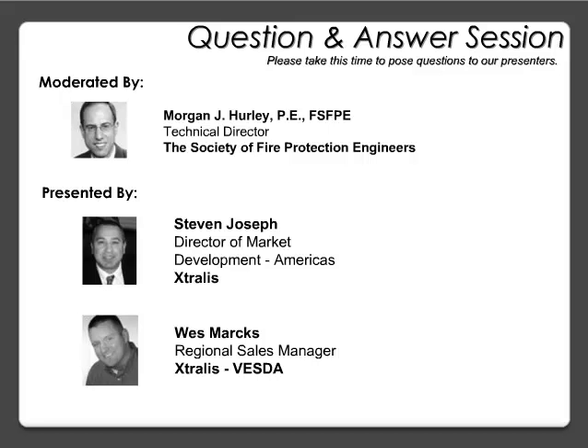And with that, we applied a time element to test and inspect each and every last sample port of a pipe run. Because this is different than traditional conventional spot-type detectors, we also had to look at power supplies, testing the batteries of the power supplies. That was included. Testing the alarm communications to the fire panel, that was included. Doing a visual inspection of the pipe network, that was included. So we did all these various elements that you wouldn't necessarily do on a traditional spot-type detector, to be conservative and have a very conservative number. I hope that answers the question.